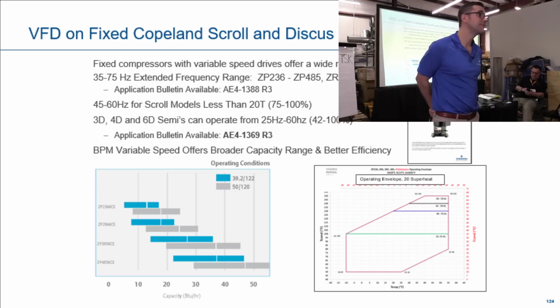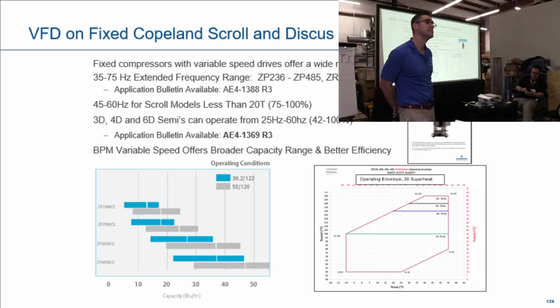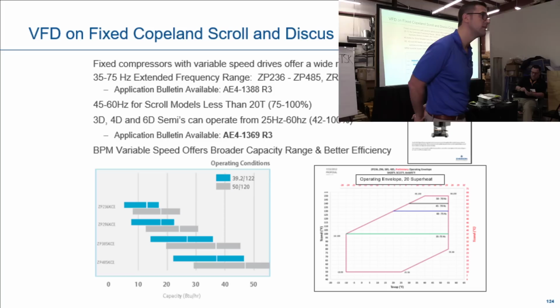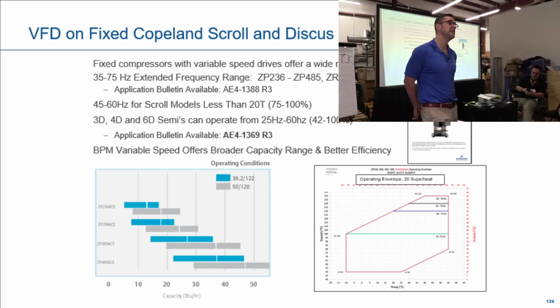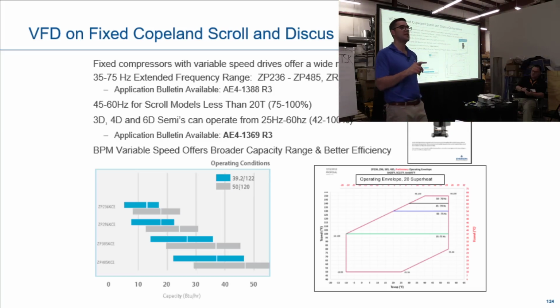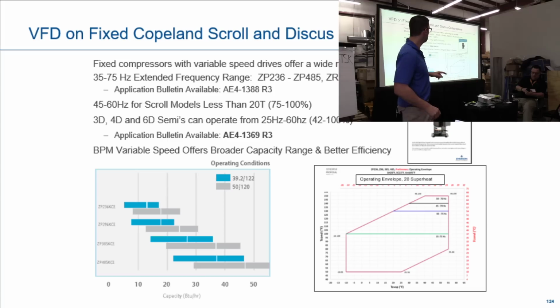Question? I got a question. I take care of an ice rink. It's an R22 system. Yep, got 650 horse on it, 8 DPs. So you're saying I can take that and put a variable speed drive on it? Which model is it? 8 DPs. I'll have to double check that. I know in our AE bulletin it only says up to 6D. But get me afterwards and I'll find that answer out for you.